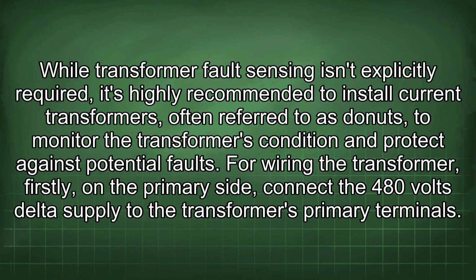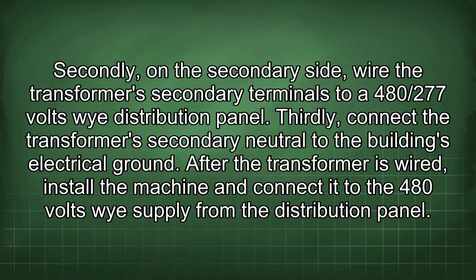For wiring the transformer, firstly, on the primary side, connect the 480 volts delta supply to the transformer's primary terminals. Secondly, on the secondary side, wire the transformer secondary terminals to a 480/277 volts Y distribution panel. Thirdly, connect the transformer secondary neutral to the building's electrical ground. After the transformer is wired, install the machine and connect it to the 480 volts Y supply from the distribution panel.